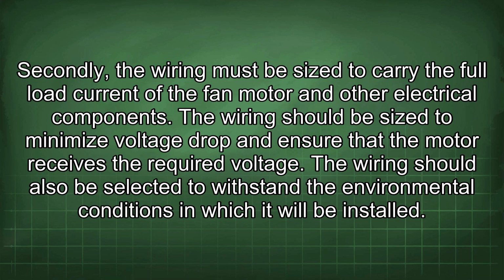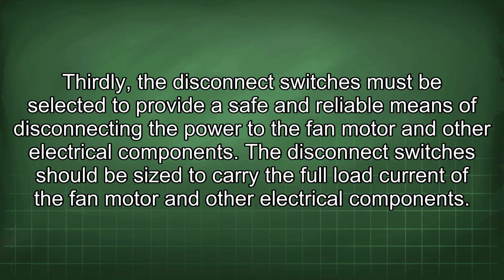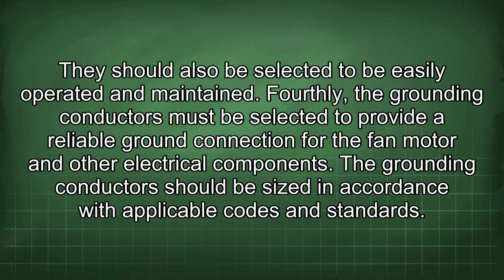The wiring should be sized to minimize voltage drop and ensure that the motor receives the required voltage. The wiring should also be selected to withstand the environmental conditions in which it will be installed. Thirdly, the disconnect switches must be selected to provide a safe and reliable means of disconnecting the power to the fan motor and other electrical components. The disconnect switches should be sized to carry the full load current of the fan motor and other electrical components. They should also be selected to be easily operated and maintained.